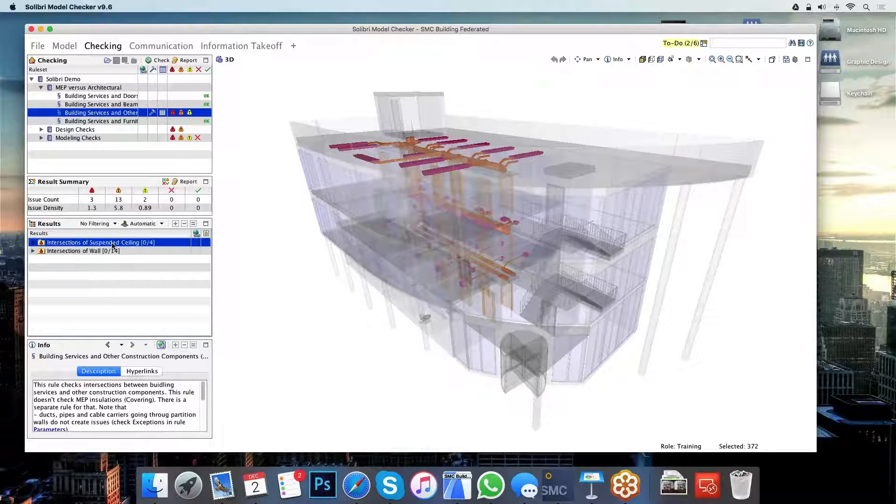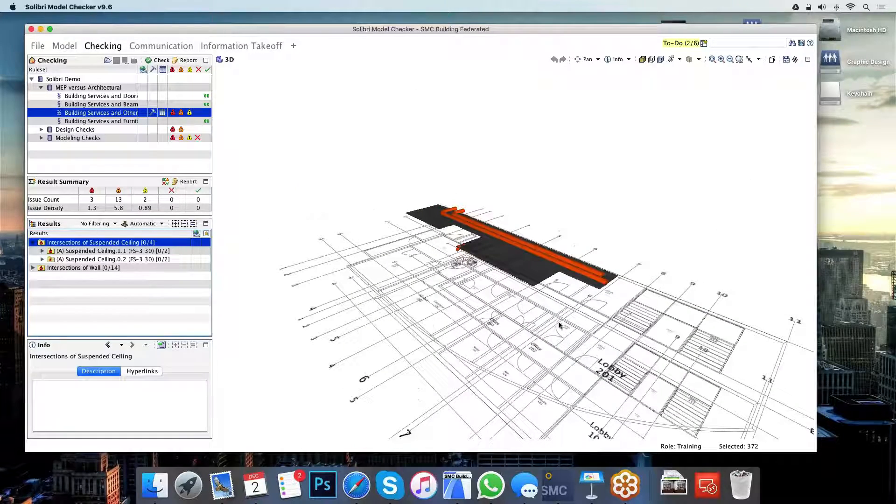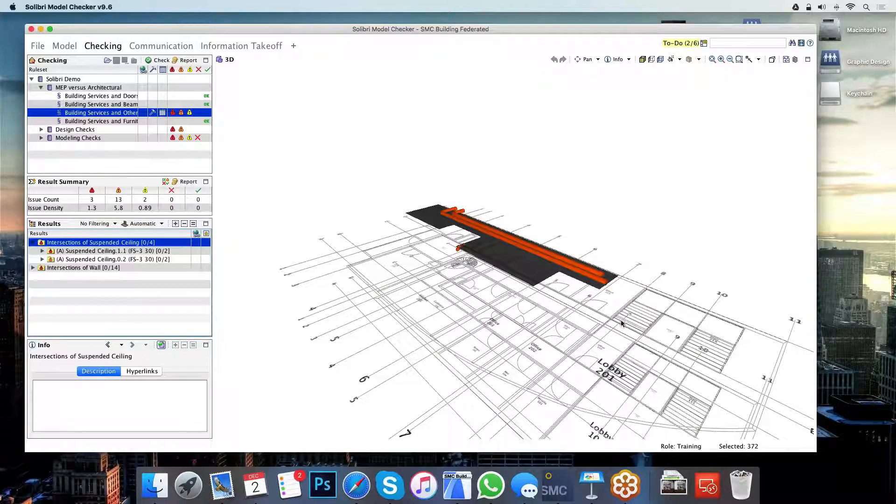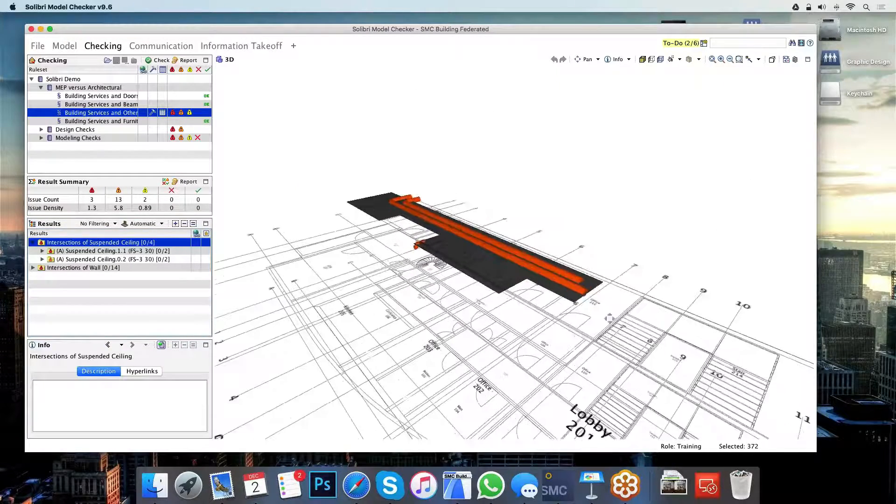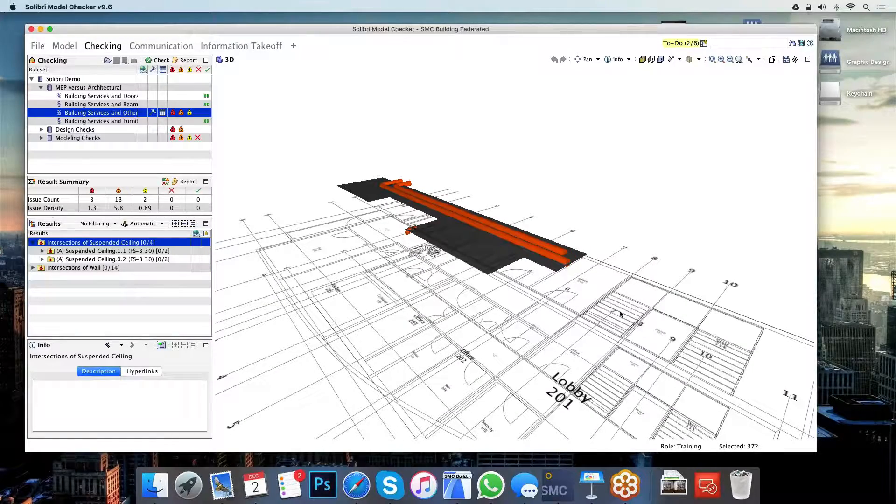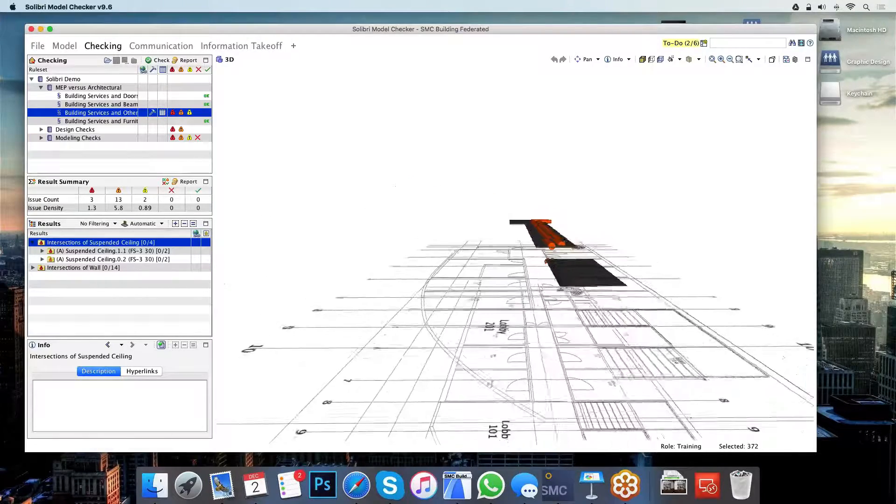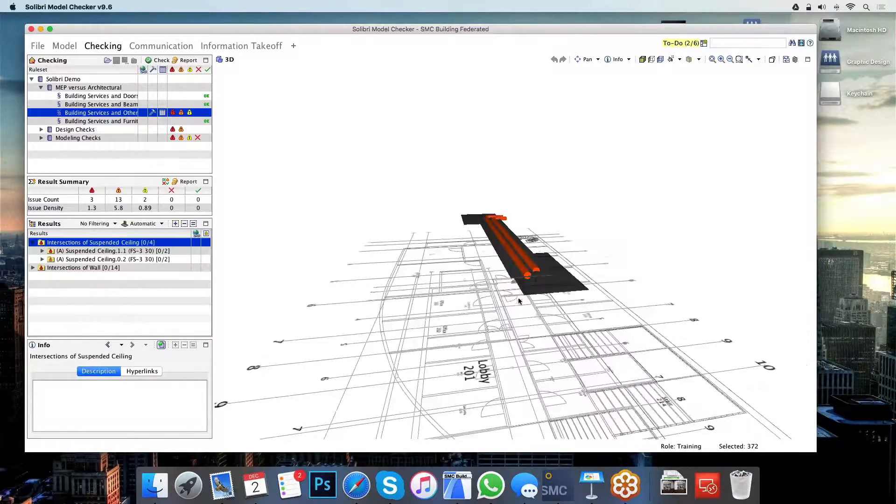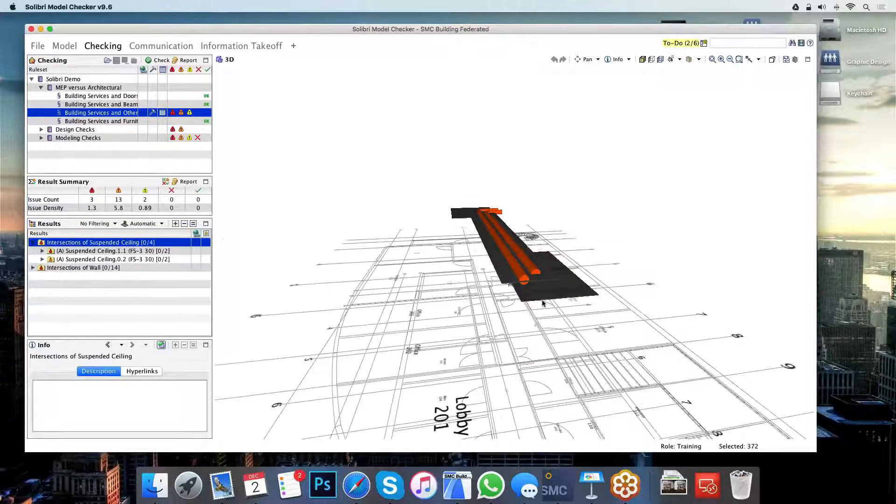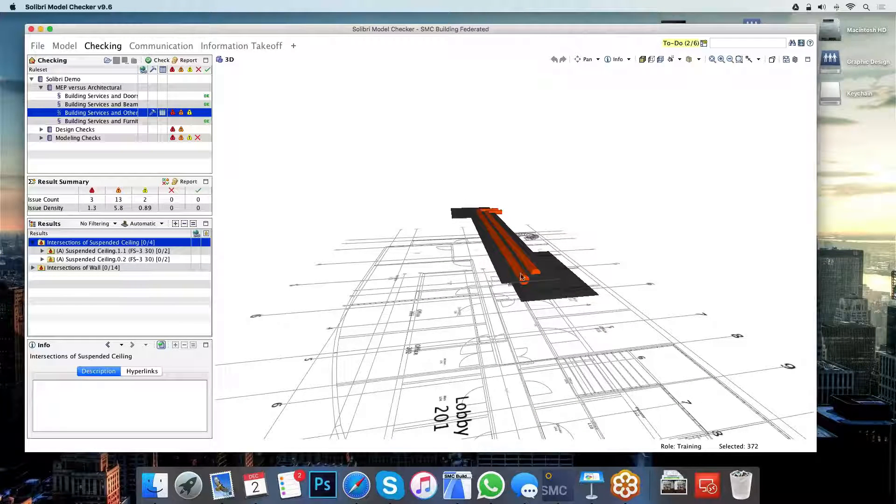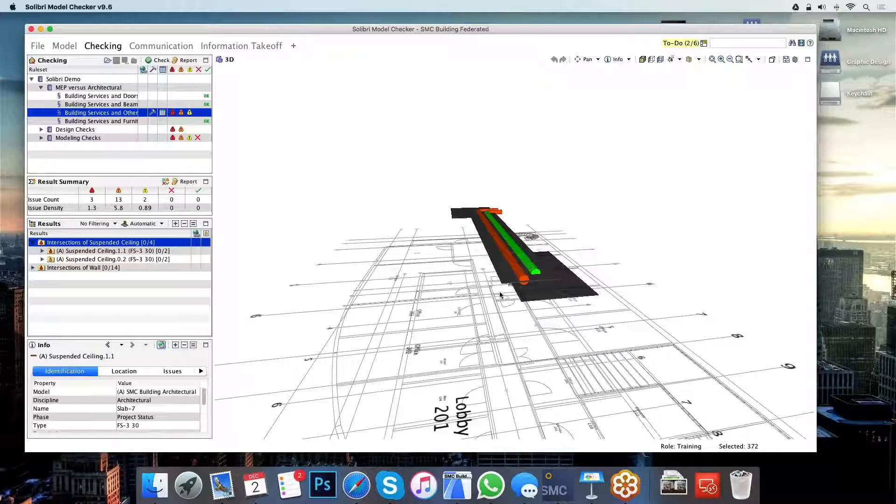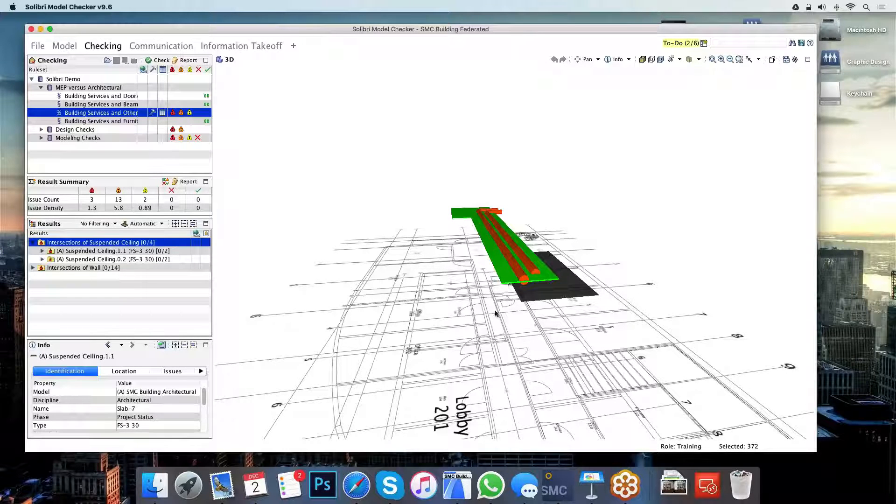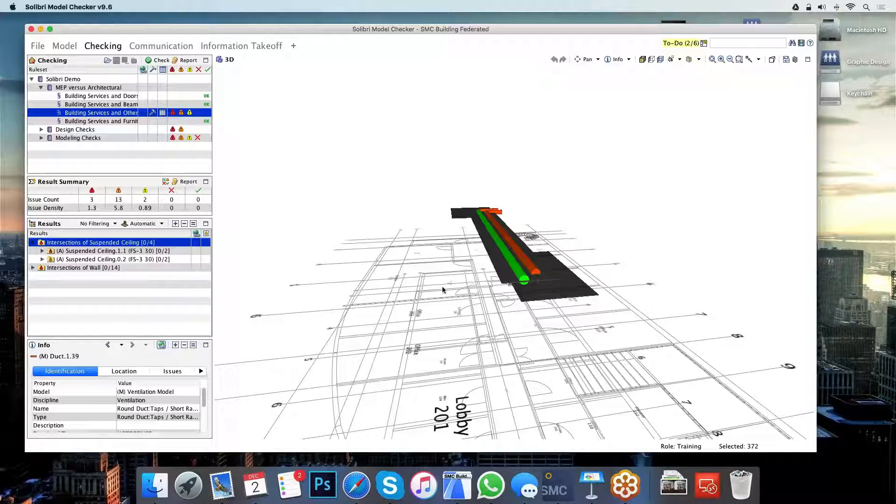The first issue here is a fairly common issue that we can have in designing buildings, especially when there's large amounts of HVAC planning going into it. This is just your traditional clash detection. What Solibri is telling me here is that these ducts here will be colliding with the suspended ceiling that is supposed to be below them.